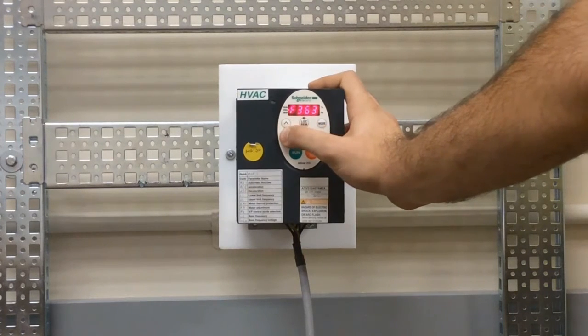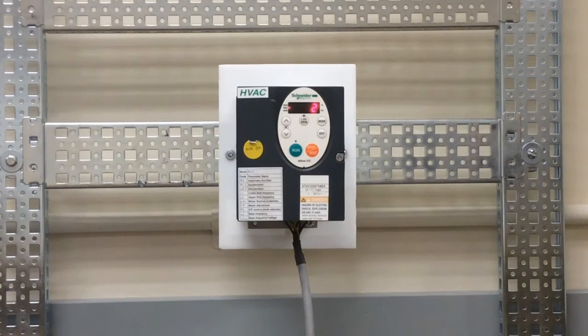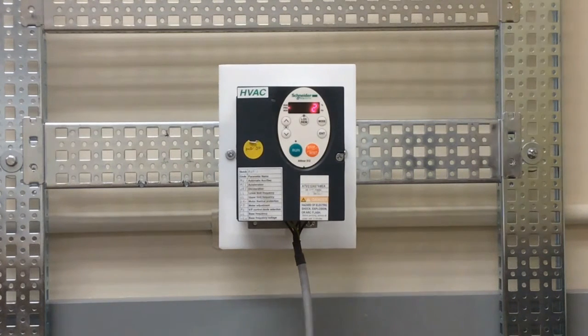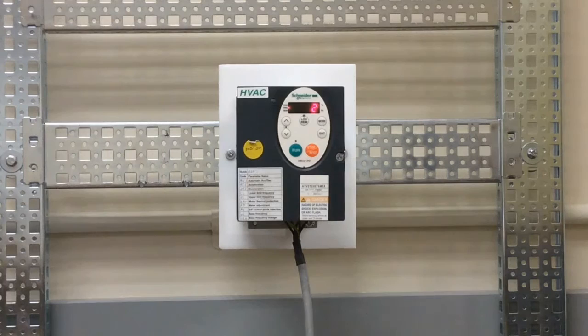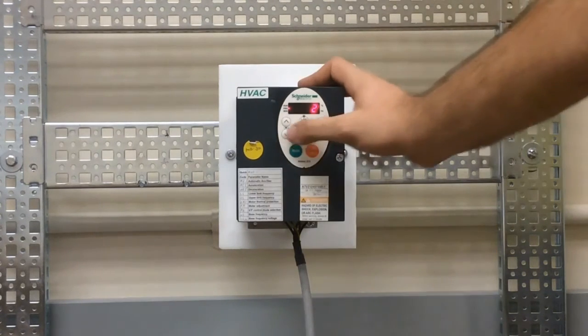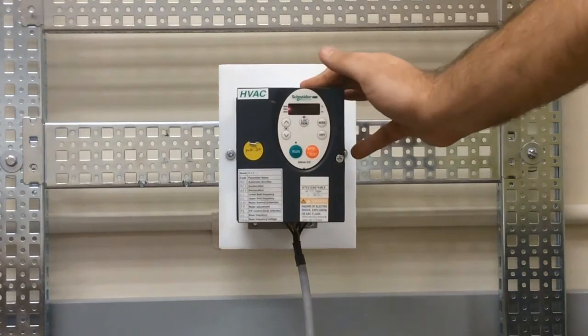Once you're on parameter F360, press enter. For your options here, you have zero, one, and two. Zero indicates that PID is turned off. One enables PID using VIA analog input as a reference, and two enables PID with VIB as a reference. We can set it accordingly. In this case, we can set to one, for example, to use VIA.